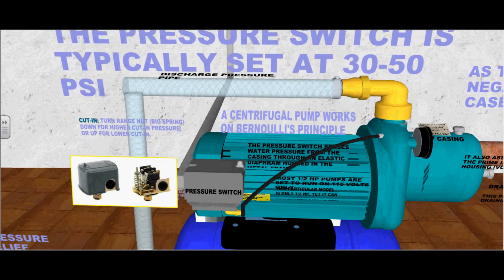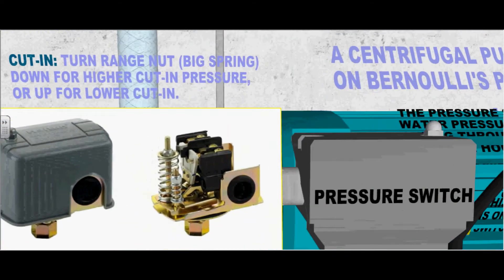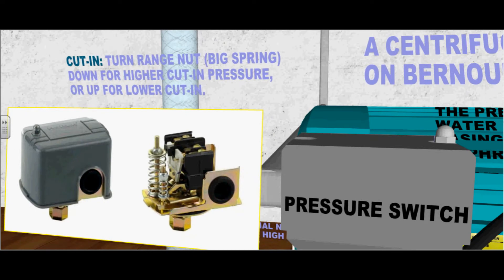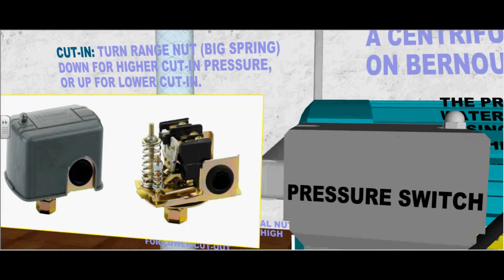This pressure switch is typically set at 30 to 50 psi. Turn the range nut or the big spring down for a higher cut-in pressure or up for lower cut-in pressure.